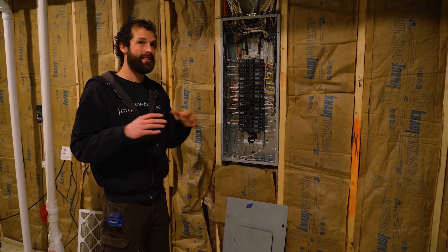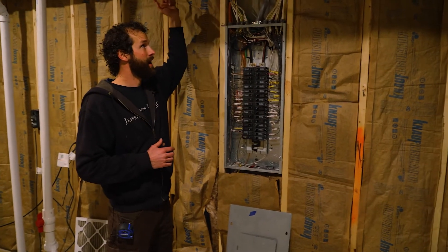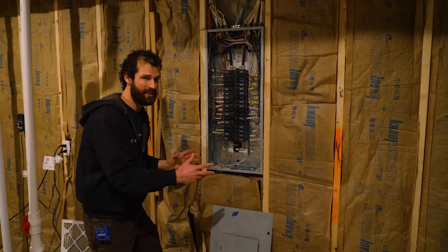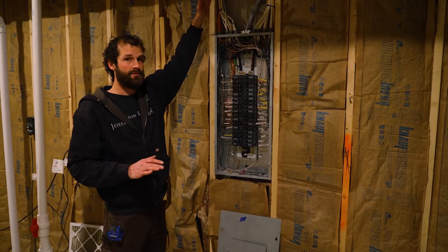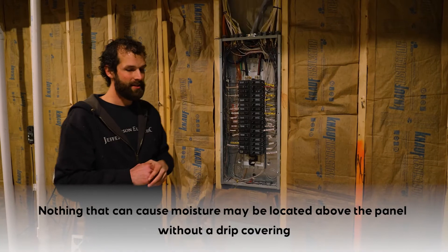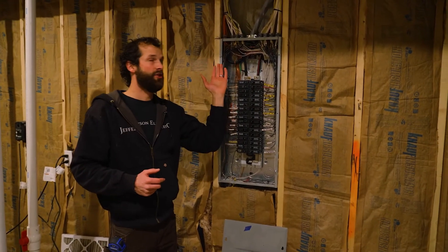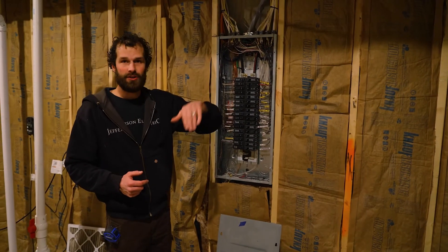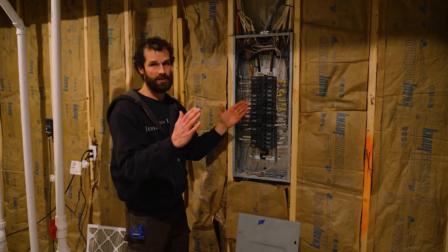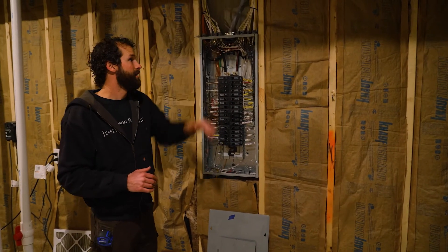Foreign systems such as plumbing or anything that could leak fluids onto the installation may not be in the vertical above the panel — not just within the six-foot-six, but above the panel at all — unless there is drip protection designed for that purpose. Realistically, that's probably not going to happen. Just keep your plumbing supply lines, drain lines, furnace condensate lines, and water heater discharge out of that area. It can be above the working space but not above the equipment itself.